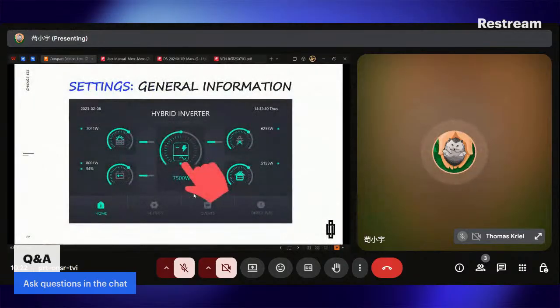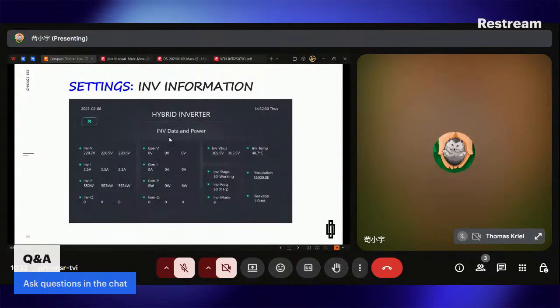And now it's about the settings. When you power on the inverter, you will see this page. In the middle, we can see the inverter icon. If we click on it, we will see more data about the inverter. We can see the voltage, current, and the power of the inverter and generator, and the temperature. And this part is pretty important, the inverter stage. When it's showing 30, that means it's on grid and working. When it's showing 10, that means currently it's off grid and working. When it's showing 89, that means it's in standby mode. Sometimes when we want to upgrade the inverter, we need to make sure it's in standby mode.